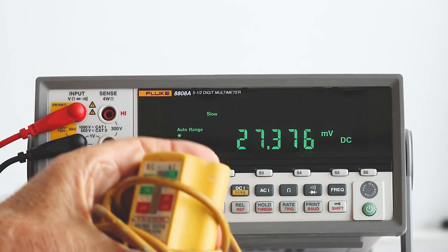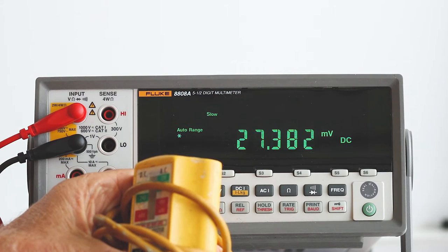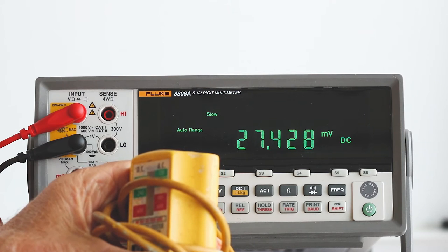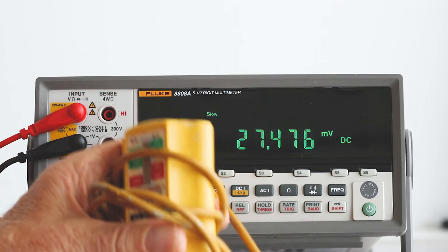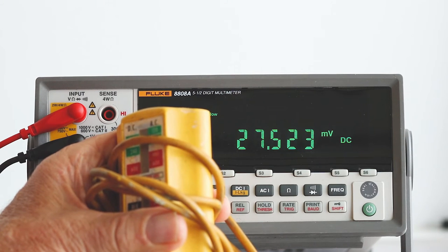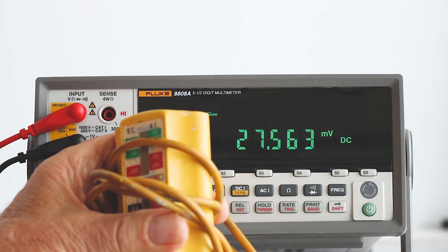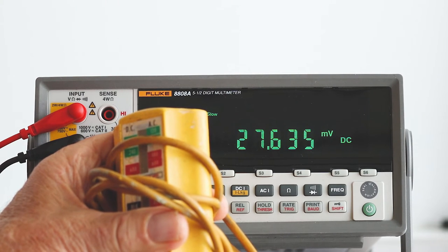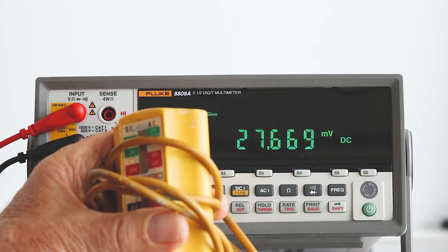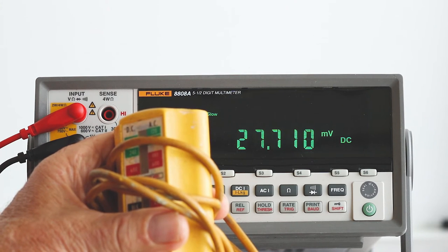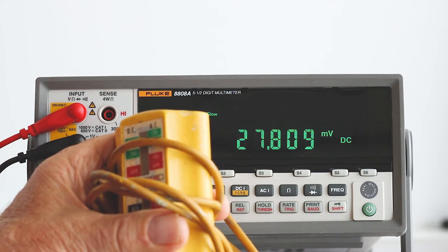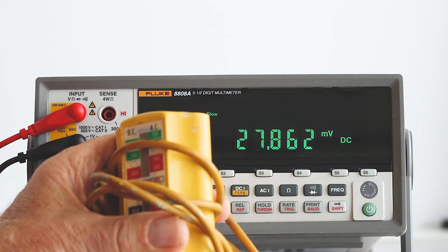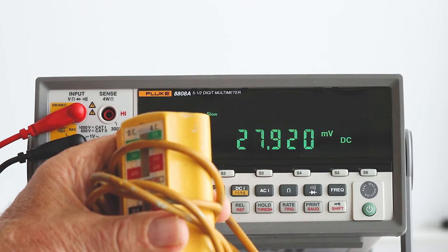The solenoid voltage tester, so-called Wiggy, is convenient for quick presence or absence of voltage tests. It makes a visual and audible report and when you touch the probes to live terminals it vibrates, so it is good in noisy environments and also when it is not convenient to keep your eyes on the meter. The solenoid voltage tester is a low impedance instrument, so it is not suitable for sensitive electronic measurements because it loads the circuit and draws a significant amount of current. It is used for house current and general purpose electrical work.